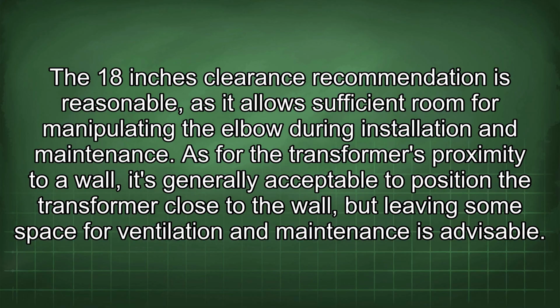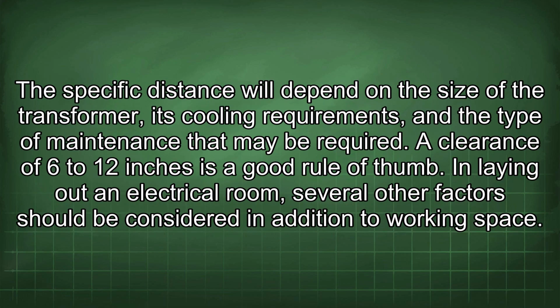As for the transformer's proximity to a wall, it's generally acceptable to position the transformer close to the wall, but leaving some space for ventilation and maintenance is advisable. The specific distance will depend on the size of the transformer, its cooling requirements, and the type of maintenance that may be required. A clearance of 6 to 12 inches is a good rule of thumb.